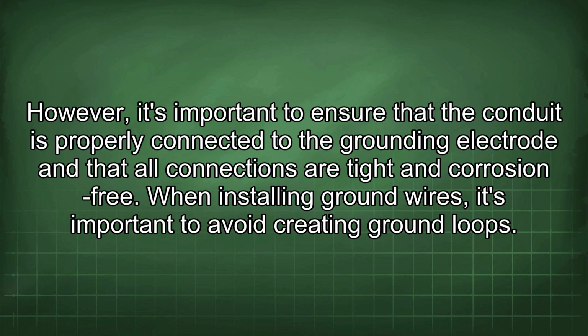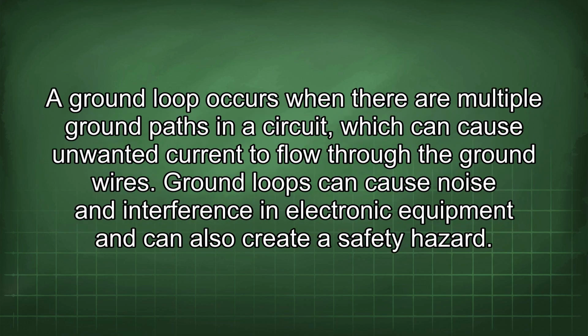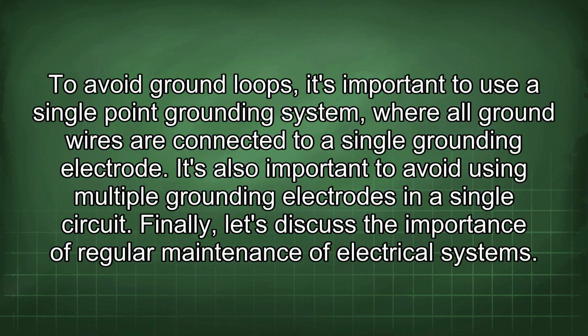When installing ground wires, it's important to avoid creating ground loops. A ground loop occurs when there are multiple ground paths in a circuit, which can cause unwanted current to flow through the ground wires. Ground loops can cause noise and interference in electronic equipment and can also create a safety hazard. To avoid ground loops, it's important to use a single-point grounding system where all ground wires are connected to a single grounding electrode. It's also important to avoid using multiple grounding electrodes in a single circuit.